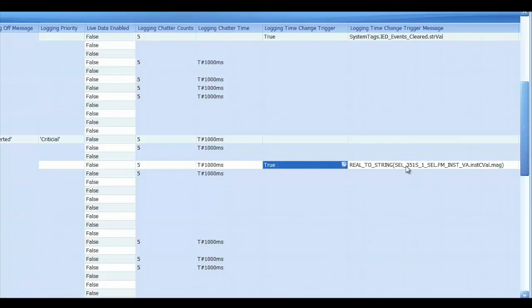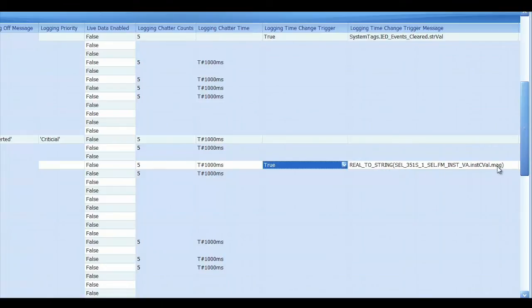And the message is I use a real to string function and I take the magnitude of that tag and feed it to that function. So if the value is say 100 and my dead band is 5, then when it goes to 110, then it will log the message of the value 110. It will convert it to a string and it will put it in the SOE log. And you can use any kind of strings or any kind of functions like that to convert things to strings. So you can log pretty much anything you want.